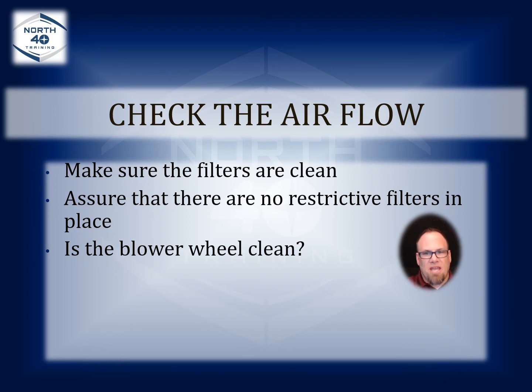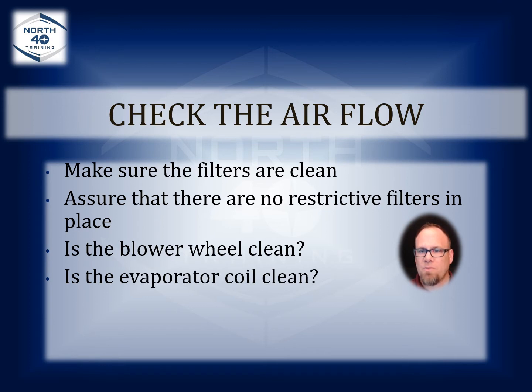And you think about it, 10%. That's a dryer sheet getting stuck in the filter. That's a restricted secondary heat exchanger that rests above the blower wheel. That's the blower wheel itself, those little scoops that have barely a turn on them, getting a little bit stopped up with dust or hair. Those things make a huge difference. And if you've got to dismantle that blower housing, take the motor out of there, take the wheel off the motor and wash it out, and that's going to be the difference for the customer, you've got to take care of that. Is the evaporator clean?